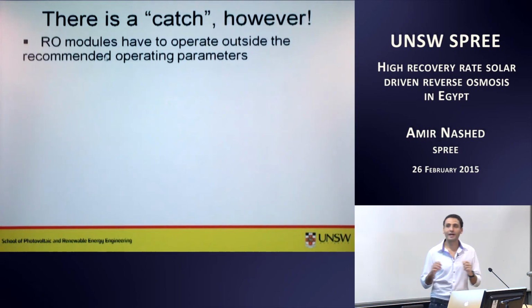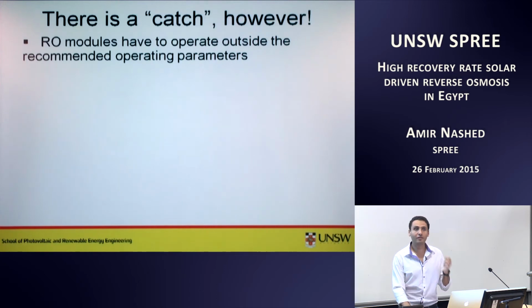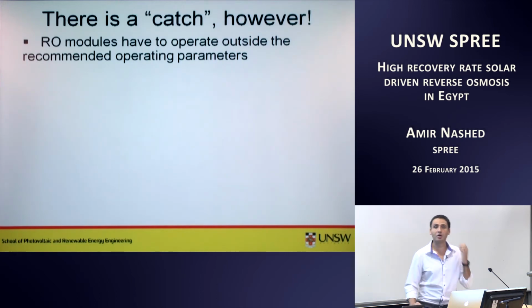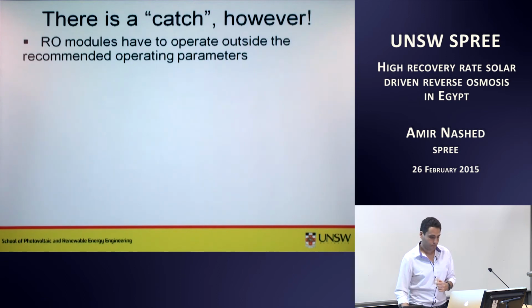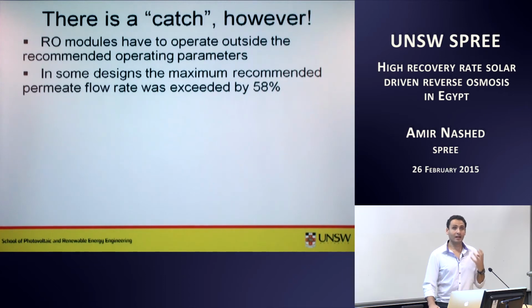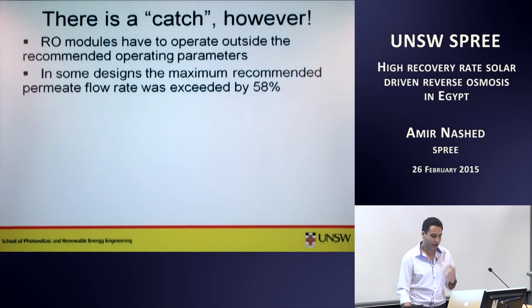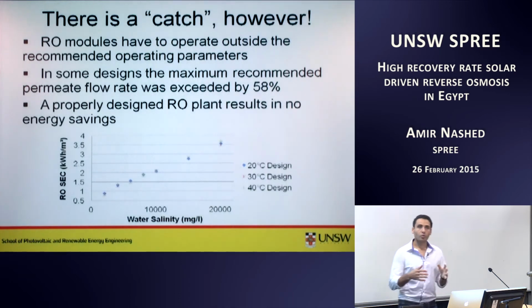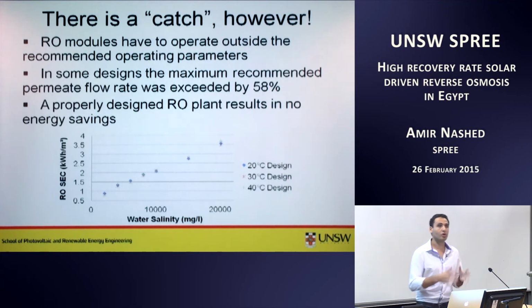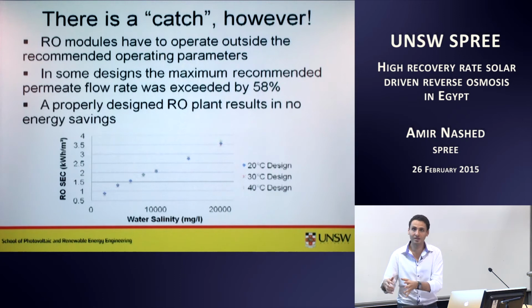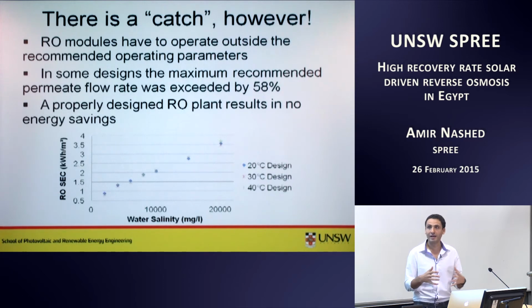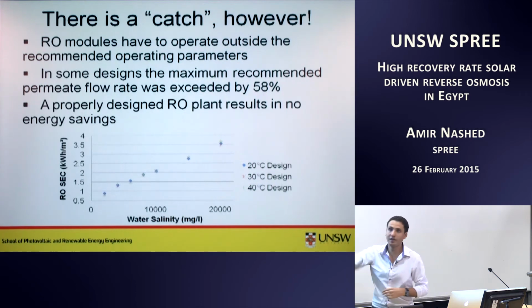What I found is that you can only get the aforementioned power savings if the RO modules are allowed to operate outside the recommended window. In some cases, I exceeded the recommended window by 58%. And why is that? When you increase the temperature and increase the permeate flow, it starts to exceed the recommended window. To counter that, if you want to properly design the system, you will have to use high salt rejection membranes. But if you use high salt rejection membranes, you limit the amount of salts that is passing, so you increase the osmotic pressure. Basically, you're countering the effect of increasing the water temperature. That's why, if I properly design the system, you can see you got no saving in specific energy consumption.